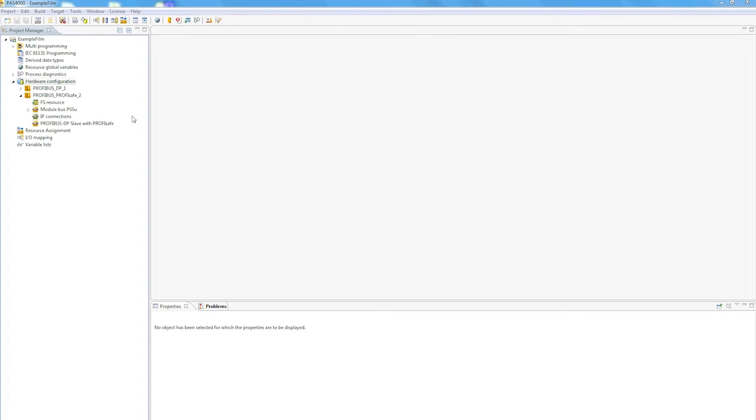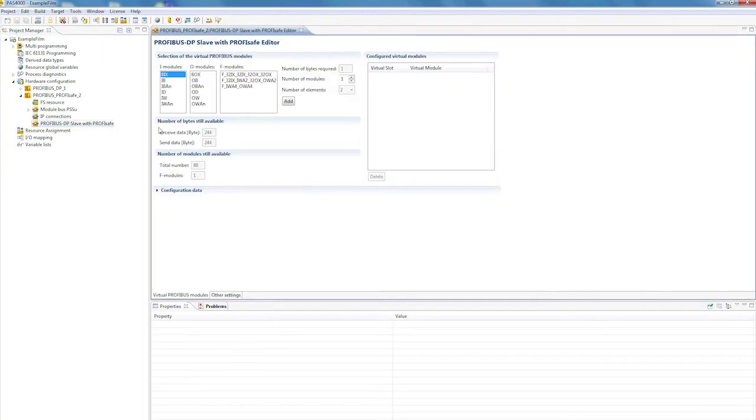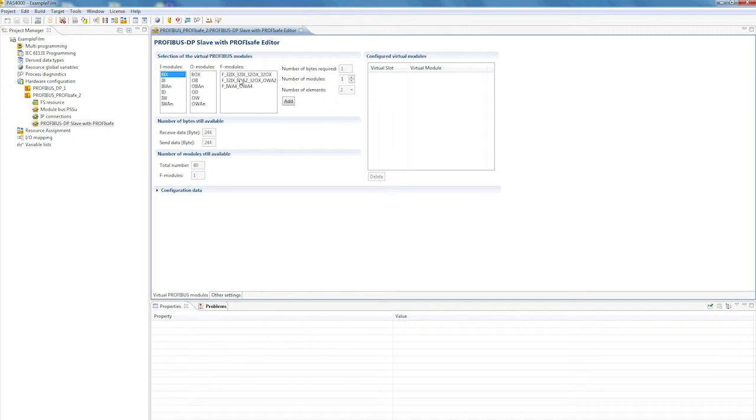The configuration is performed in the ProfiSafe editor. Pre-configured F modules are available in the PSS 4000 for safe ProfiSafe communication. These are pre-configured with virtual I.O. modules and contain send and receive data. A maximum of one F module can be configured for safe communication.